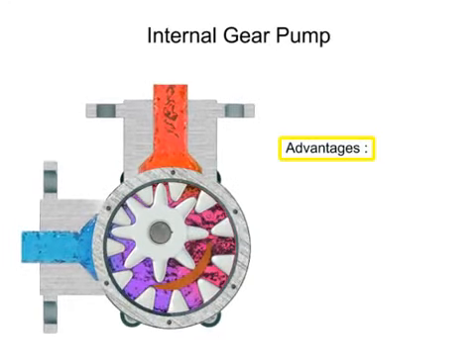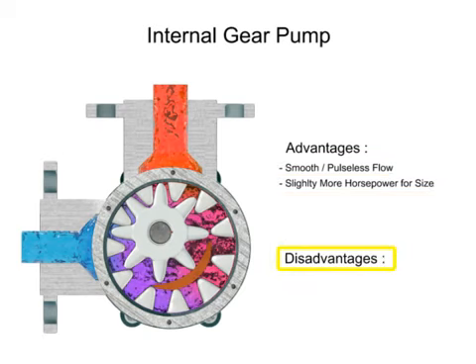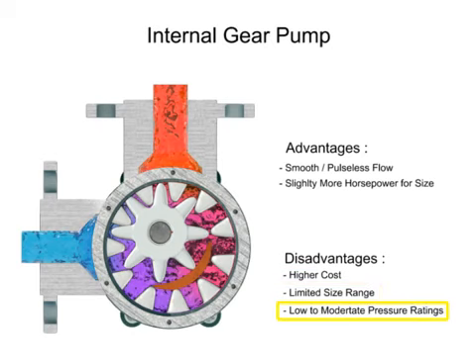Advantages of internal gear pumps include smooth and almost pulseless flow and slightly more horsepower for their size. Disadvantages are higher cost, limited size range, low to moderate pressure ratings, and few sources of manufacture.